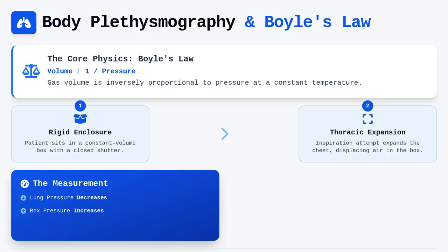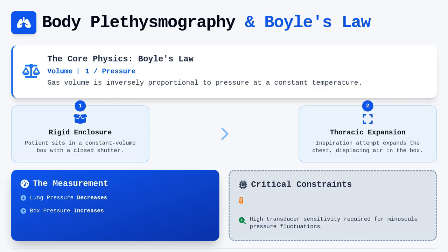We essentially treat the entire body as a displacement device, where the expansion of the chest wall compresses the air inside the chamber. The transducer sensitivity required for these measurements is significant, as the fluctuations in box pressure are often minuscule compared to atmospheric pressure. Consequently, the hardware must be meticulously designed to maintain isothermal conditions, as any heat transfer during the compression or expansion cycles would violate the assumptions inherent in Boyle's law.